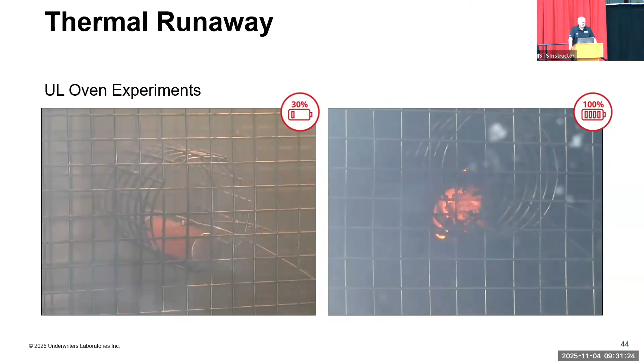As we see that smoke coming out of the batteries, what's coming out? In a nickel cobalt aluminum battery, NCA, about 30% of that is hydrogen. Another 15% is a combination of other hydrocarbons and fuels. About 26% is carbon monoxide, and about 29% is carbon dioxide.